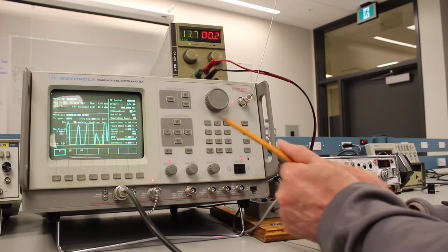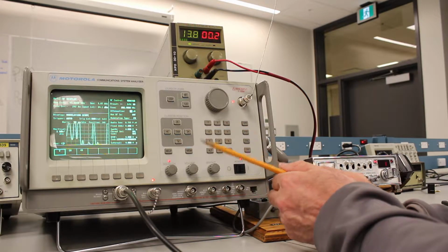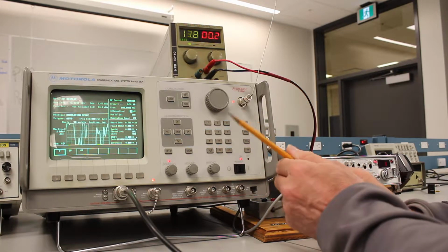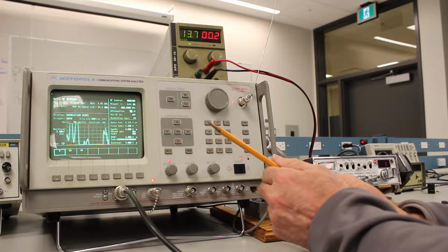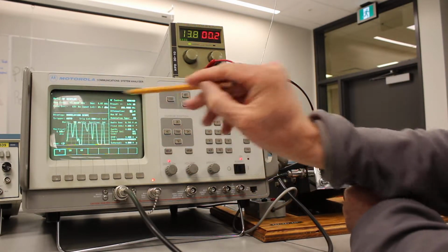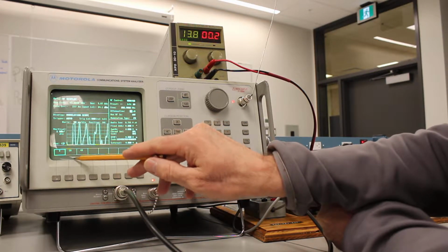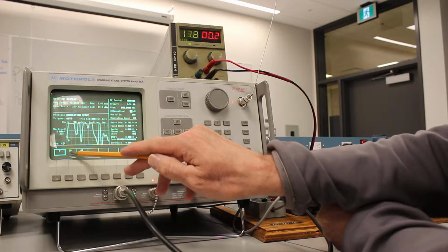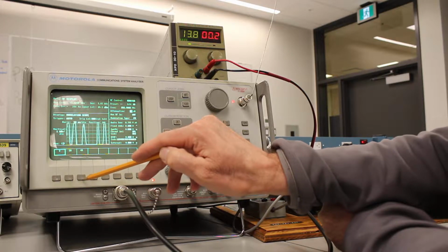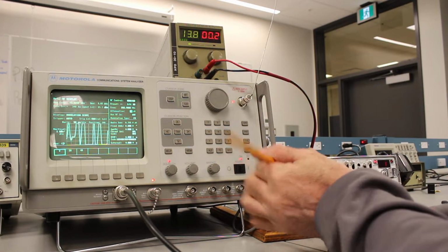The next line in the RF zone indicates whether or not we want to add attenuation to our signal. It's set to 0 dB right now, but we can add attenuation in increments of 20 dB by changing it on the soft keys as indicated below.